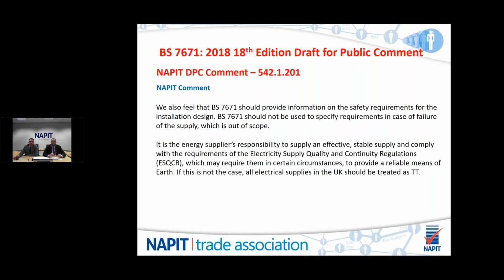We feel that BS 7671 should provide information on the safety requirements for the installation design. BS 7671 should not be used to specify requirements in the case of the failure of a supply, which is out of the scope of our regulations. It is the energy supplier's responsibility to supply an effective, stable supply and comply with the requirements of the Electricity Supply Quality and Continuity Regulations, ESQCR, which may require them in certain circumstances to provide a reliable means of earth. If this is not the case and they're unable to provide this, then all electrical supplies in the UK should be treated as TT, and therefore the installation of earth electrodes.